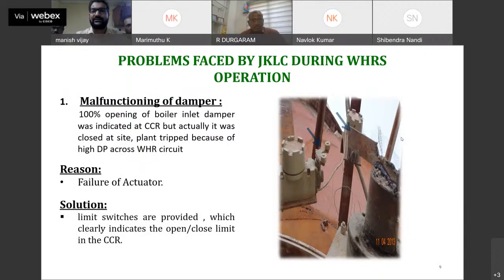These are the experiences which we have faced during the commissioning or the stabilization of the WHR process. First is the malfunctioning of the damper. As we all know, the damper is a critical part for our cement industry, and if it is malfunctioning, then it can stop the plant and damage the system by damaging the ducts and other things. So we also faced this during the initial stage of the plant.